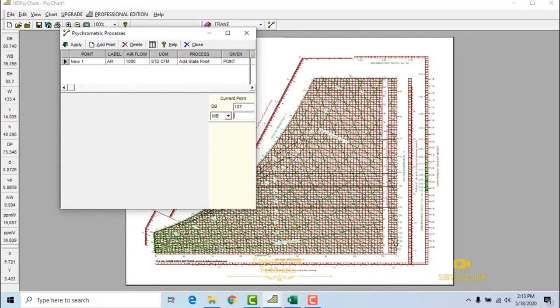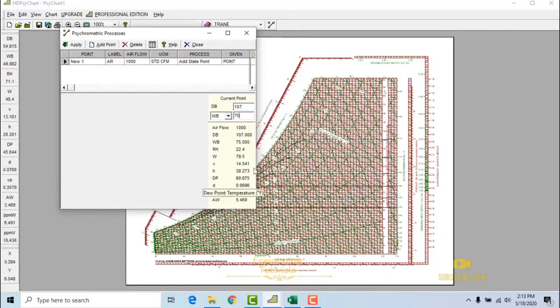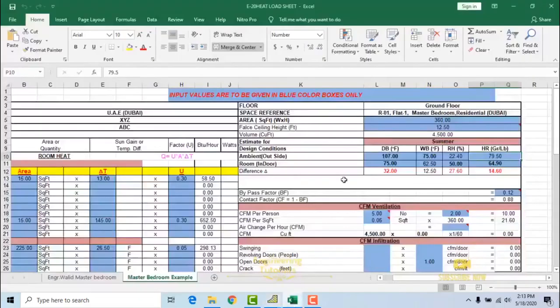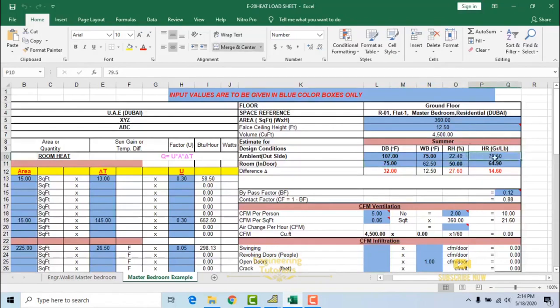We input the outside design dry bulb temperature for Dubai as 107 degrees Fahrenheit and wet bulb as 75 degrees Fahrenheit. As you can see, the other parameters are also calculated. Our concern is the humidity ratio and relative humidity. With dry bulb 107 and wet bulb 75, the relative humidity is 22.4% and the humidity ratio W is 79.5 grains per lb. As you can see in our Excel sheet E24, we have input relative humidity as 22.4% and humidity ratio as 79.5 grains per lb.